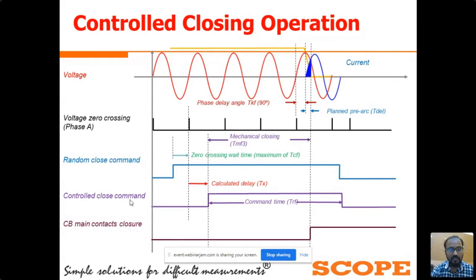Once the CSD executed the command to the circuit breaker, just before the CB contacts get in physical touch with each other, we can see this pre-arcing current start to flow through the CB contact. At this moment the CB contacts are not physically in touch with each other, but the dielectric strength between the contacts is less than the system voltage. Due to that, there is no asymmetry, no DC offset, observed here.